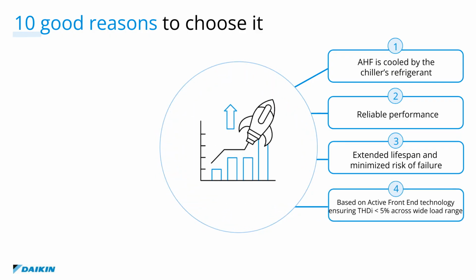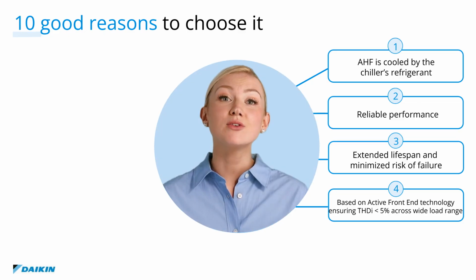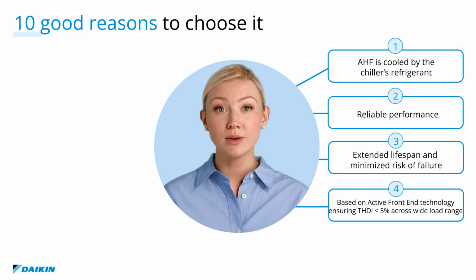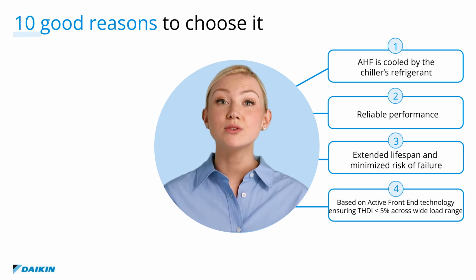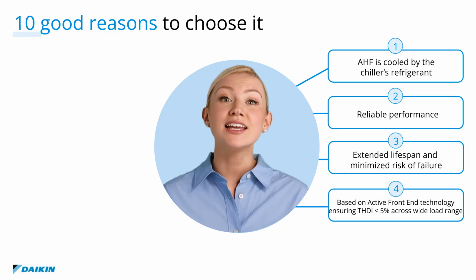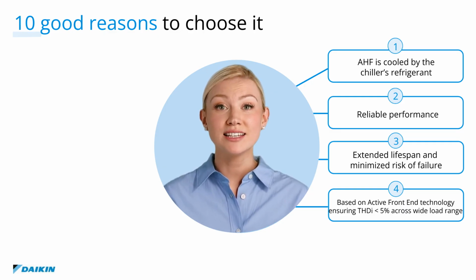Now, let's talk about control and performance. The Daikin AHF is based on active front-end technology, maintaining a total harmonic distortion of current below 5% across a wide load range. This isn't just at full load, it holds even during partial operation, which is typical for data center chillers. That means predictable, stable current draw without overheating cables or corrupting signals to sensitive devices.